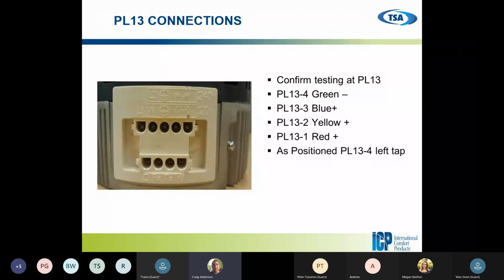Same thing here. Once we're done testing it at the board, we want to test it at the motor to make sure that plug is in correctly, or the wires are, maybe there's something going on between the wires. Very uncommon that we see a wiring harness fail. If anything, in the wiring harness it's usually where the connections are. They're not pushed in enough, or it's just not sitting in there properly, and we need to replace it so it fits a little bit tighter. Very uncommon for the wire between the two plugs to be affected, unless there's something outside the box that has actually happened to it.